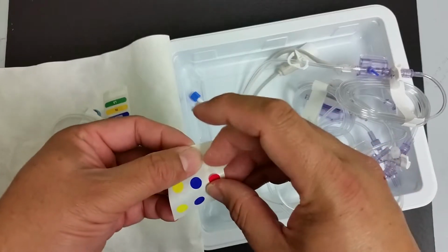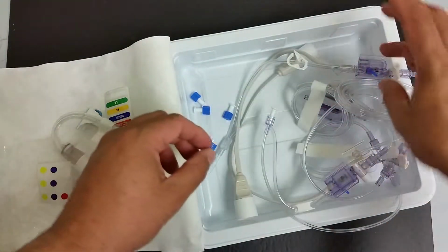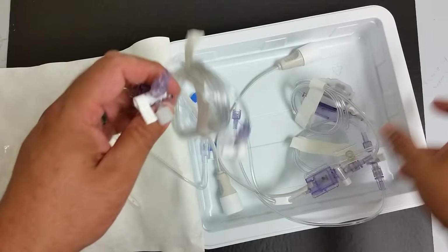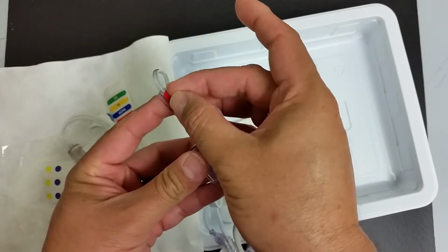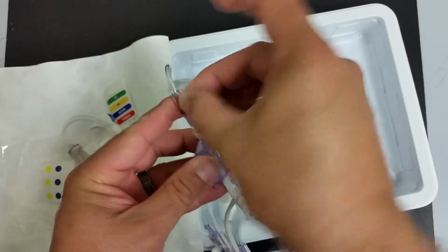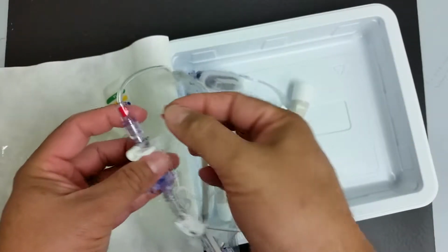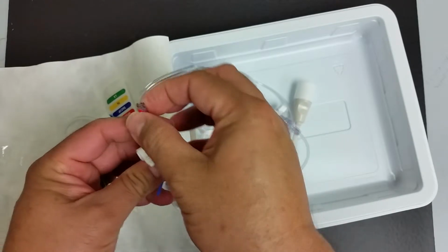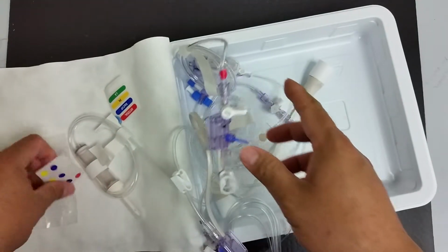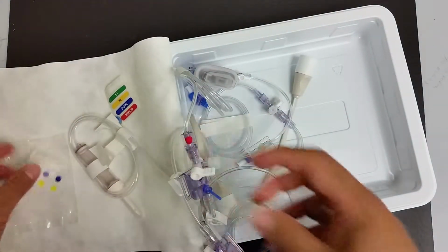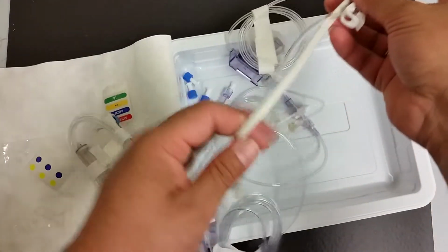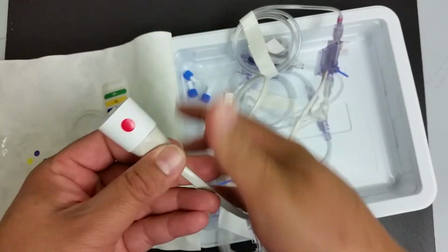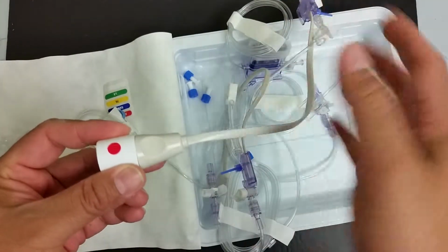Same as with the single transducer, we're going to label red on the tubing right after the transducer to make it easier to identify when you're going to connect it to the pressure cable. We follow through and put a nice little red dot in here. Because this is not used that much, we don't need to label it too much.